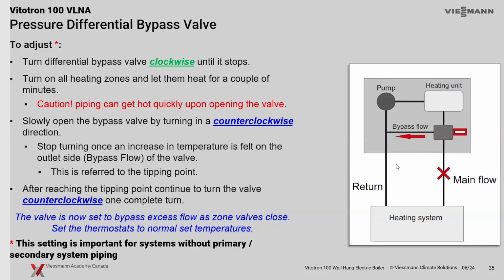So the whole idea is you have to set this at the tipping point, and from that point the valve will operate automatically based on when you have 5 zones and only 3 of them are opening. This valve will open up to a specific pressure to make sure we unload that pump head. So we're not going to have any issues with getting that pump into areas where it's inefficient or causing problems as far as deadheading, etc. on this unit. So it's good if you're doing a direct connection of your heating system to the unit itself, with no primary-secondary. You can adjust this so you have good flow through your whole system, and this is operating correctly.